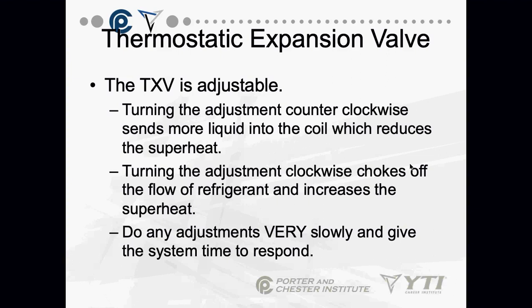Do any adjustments extremely slowly and give the system time to respond. How long should I wait for a refrigeration system to respond to a change in the TXV before I make another change? 10 to 15 minutes.